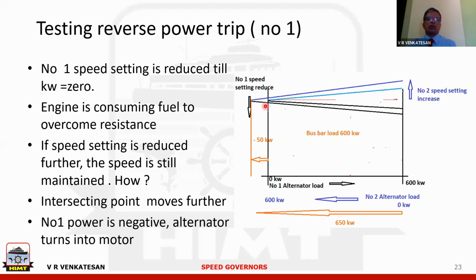Now, if I want to simulate the reverse power, what we normally do is we reduce the setting even further. That means this black line is moved even further. So for number 1 generator, we reduce the speed setting even more. As you reduce it even more, I am reducing the fuel to the engine, but the speed is still maintained. Engine is not slowing down. How is that possible? Because, sir, the second generator which is running drives the first one. Correct. So the energy required to keep rotating is now coming partly from the other generator.